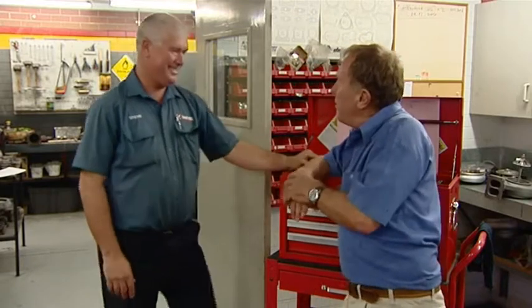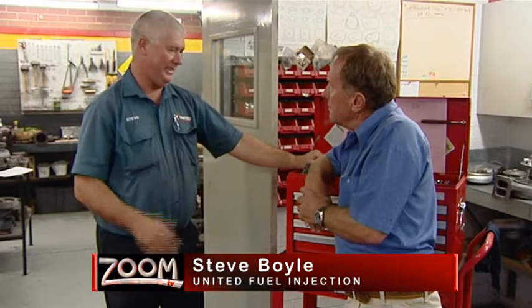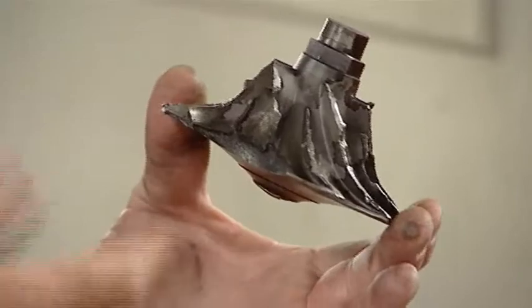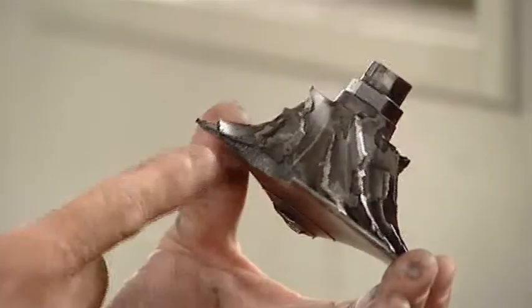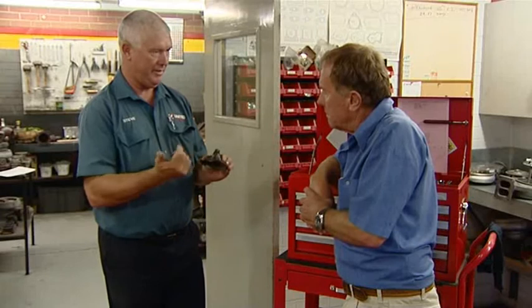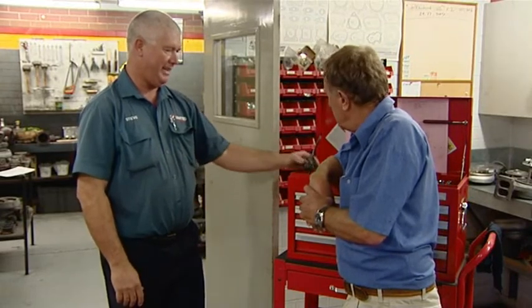What is the main failure with one? Well, these days with the stuff that works hard — the industrial diesel stuff — it's generally impellers that we've found the limit of. There's a process called low cycle fatigue where, according to the number of times that the thing's been accelerated through its critical speed, eventually the aluminium impellers fatigue and throw a piece out the side. That throws the thing out of balance and it's a catastrophic failure.